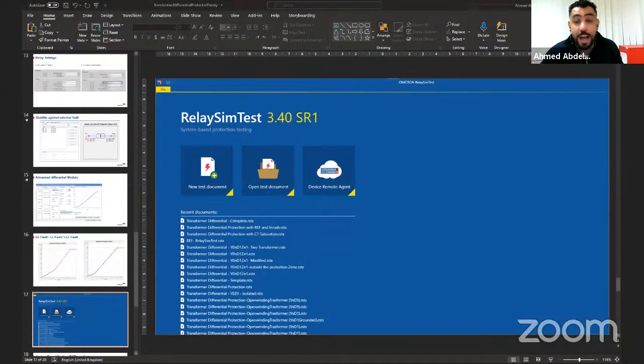And you will see here that I was testing a transformer of YY0D5. So I have a transformer, 3 windings, star 0 D5. And I want, for example, now to change the location of the fault. Because it's already tested, I need to go here, clear. You can see here, the fault is on the left side. I need to have the fault here on the right side.